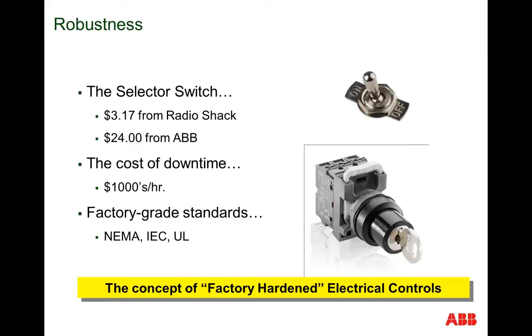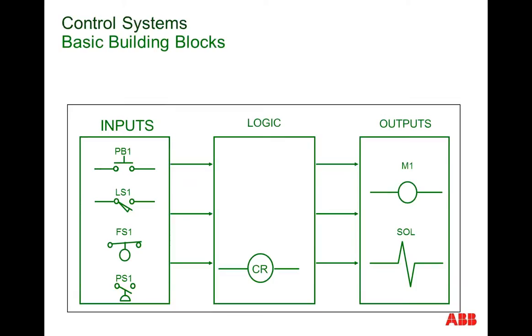Now let's talk for a moment about the sensors on the machine. You can buy a good old selector switch from Radio Shack, as you see here, for a few bucks, and it'll do what's needed on the machine, well, for about a day or two. You see, electrical controls are what we call factory hardened, meaning that they're designed to be heavy duty and rugged to survive a nasty, noisy, and dirty shop floor. The standards by which these devices are designed are shown here. NEMA and UL are North American standards bodies, and the IEC stands for International Electrotechnical Commission, and that's the European standard.